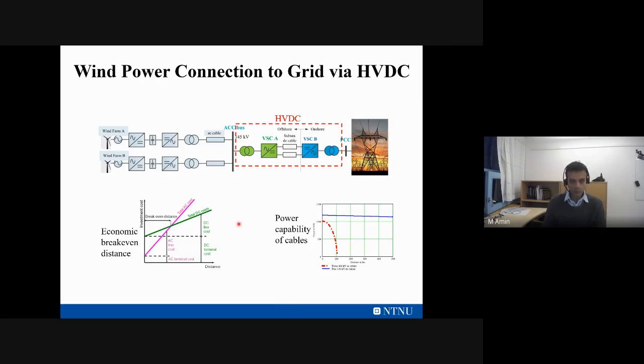Another thing is that if we have to transmit power over a long distance, we see that after a certain distance - this pink color is the total cost for AC transmission system, and the green one is for the high voltage direct current transmission system. If the transmission distance is higher than a particular length, several hundred kilometers, the cost - installation, investment, all the cost - is much higher for the AC transmission system. So it's better to go with the high voltage direct current transmission system.